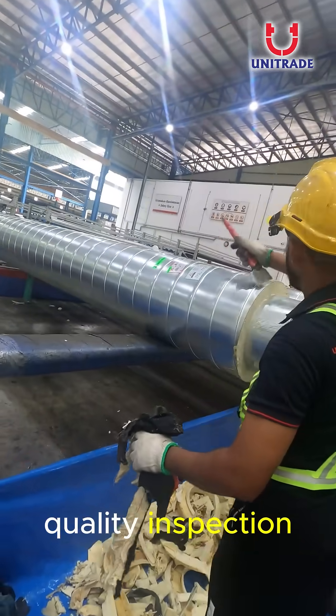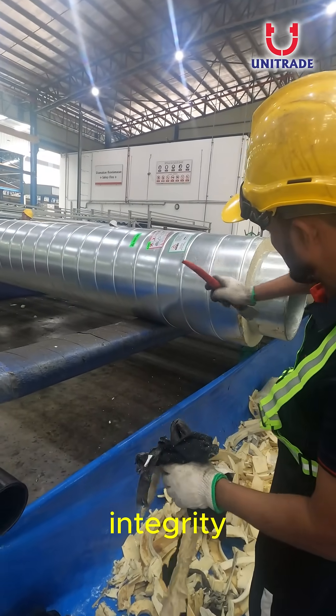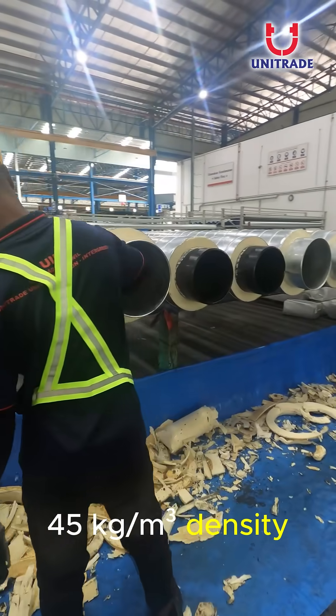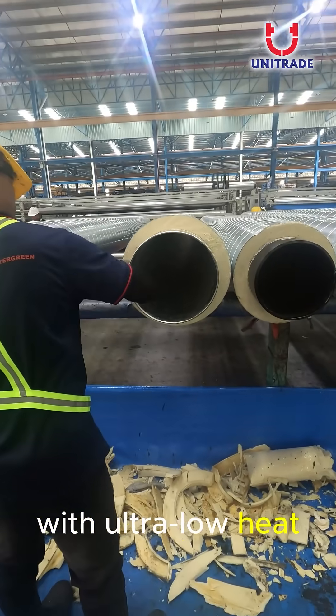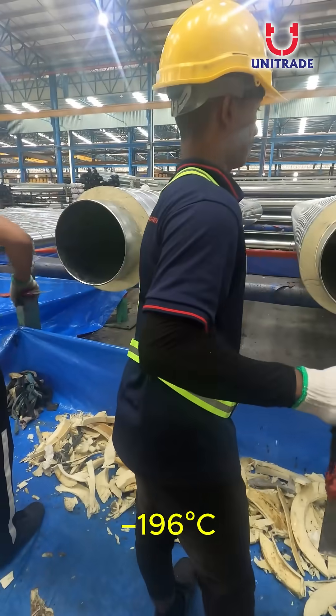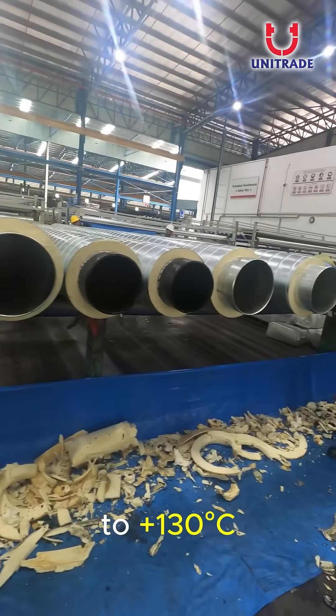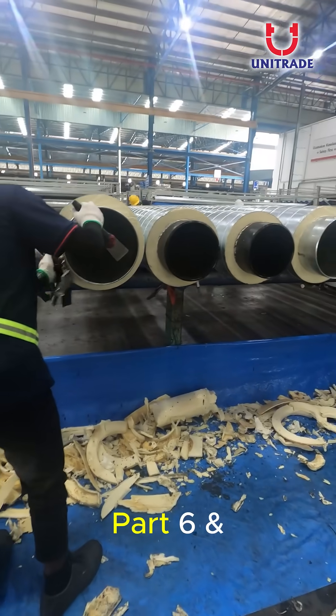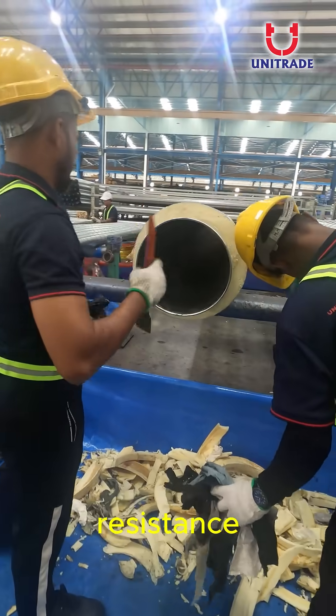Every pipe undergoes quality inspection to ensure insulation integrity. Our insulation delivers 45 kilograms per cubic meter density with ultra-low heat transfer, built to perform from negative 196 degrees to 130 degrees Celsius, certified to British Standard BS 476 Part 6 and 7 for fire resistance.